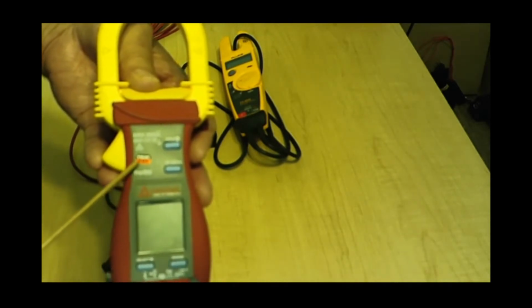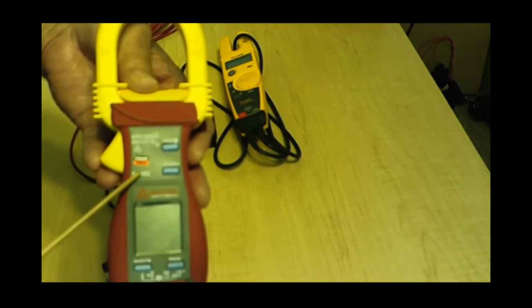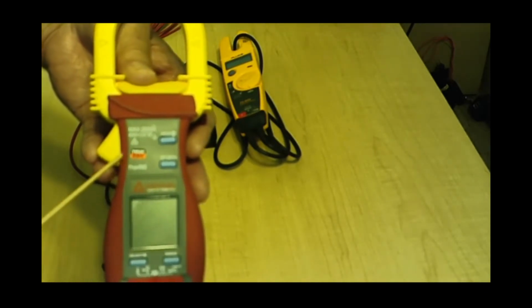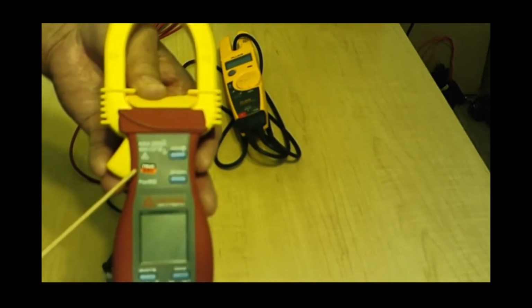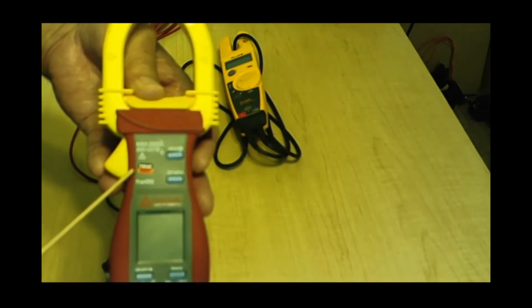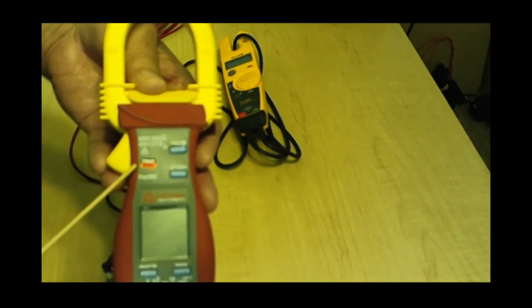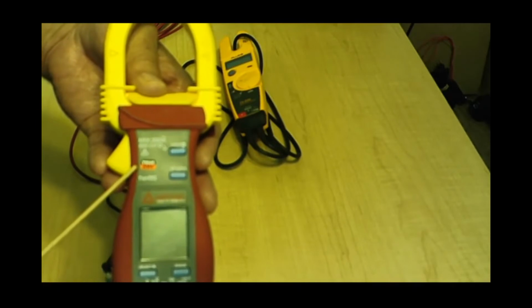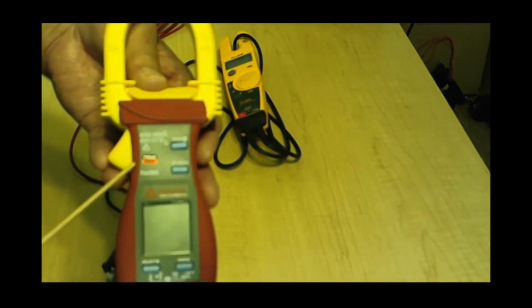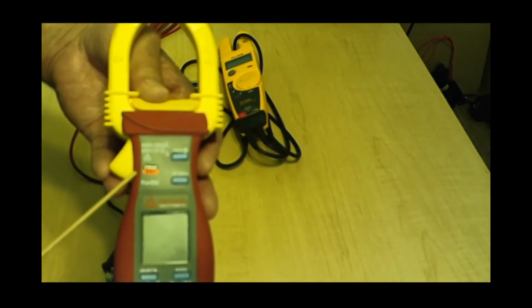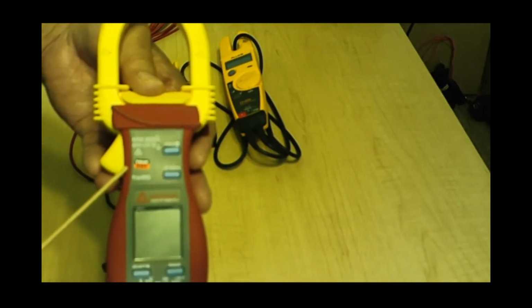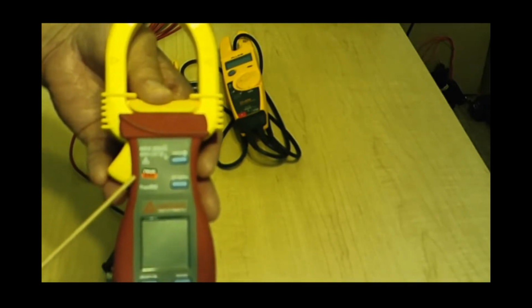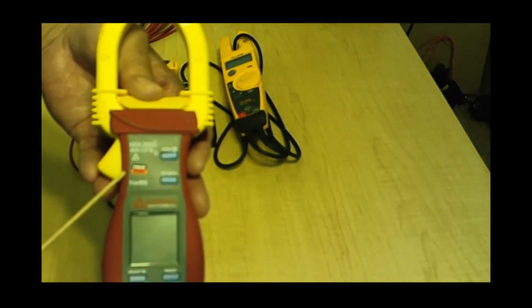Now, this meter is also identified as what's called true RMS. Most meters are not true RMS. They will only read a sinusoidal sine wave. This meter will read all types of waveforms. What that means to you is, if you're measuring a normal power circuit, any meter will work.